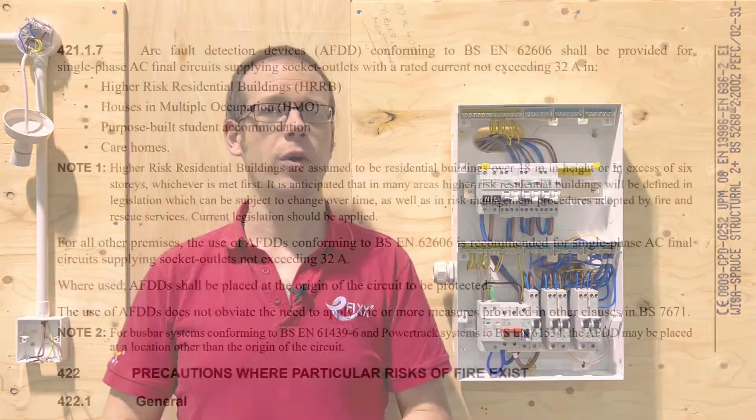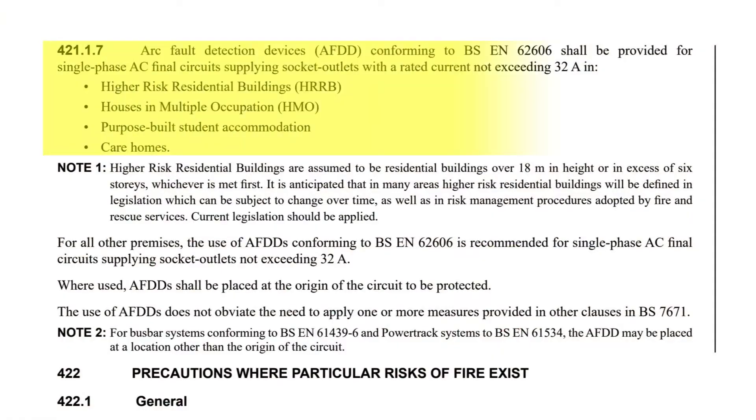Well regulation 421.1.7 states that arc fault detection devices AFDD conforming to BSEN 62606 shall be provided for single phase AC final circuits supplying socket outlets with a rated current not exceeding 32 amps in higher risk residential buildings, houses of multiple occupation, purpose-built student accommodation and care homes.